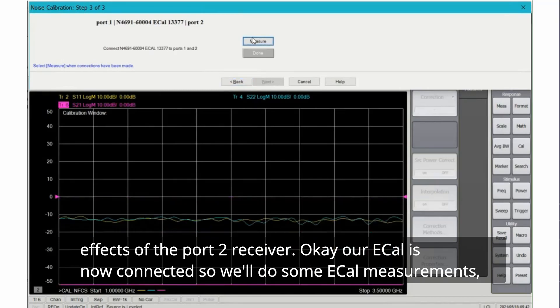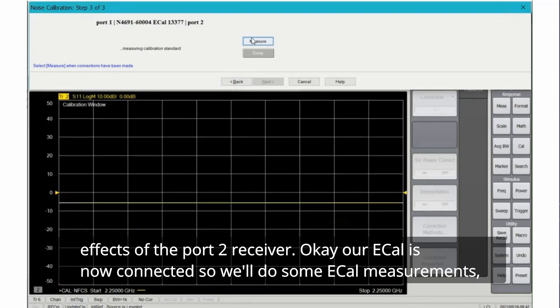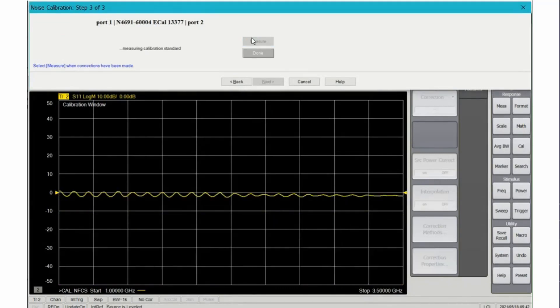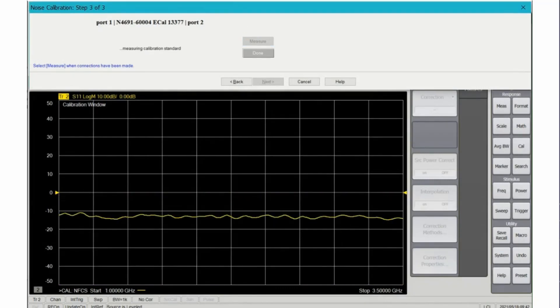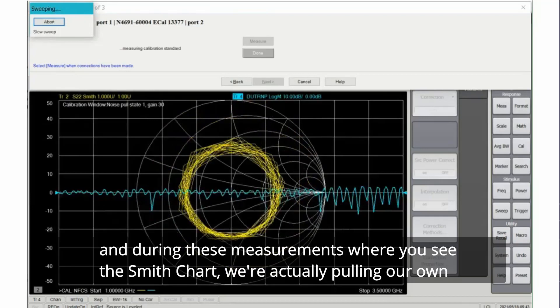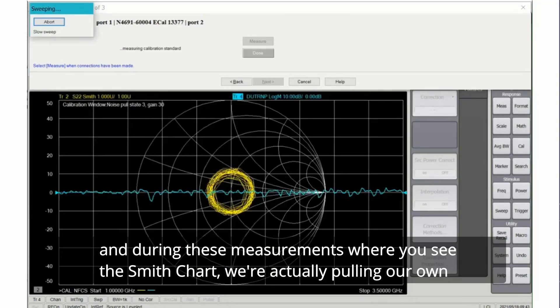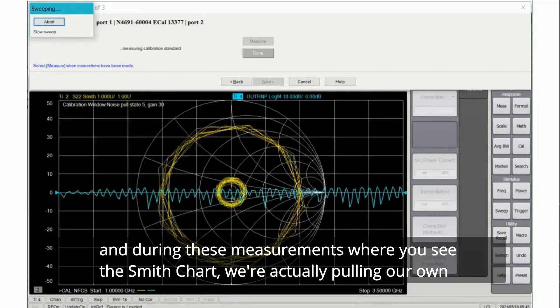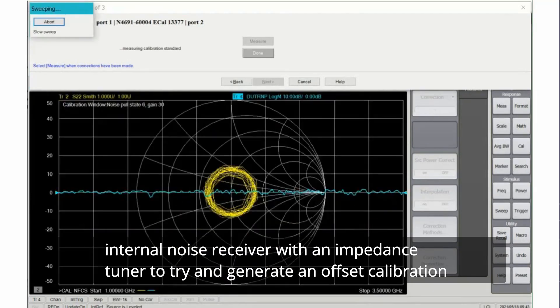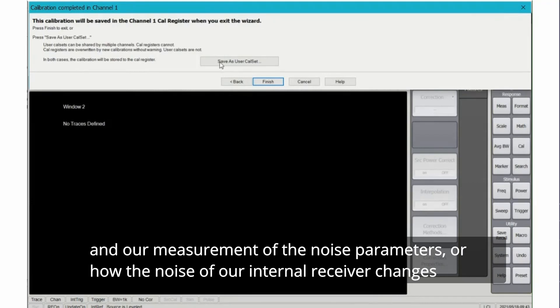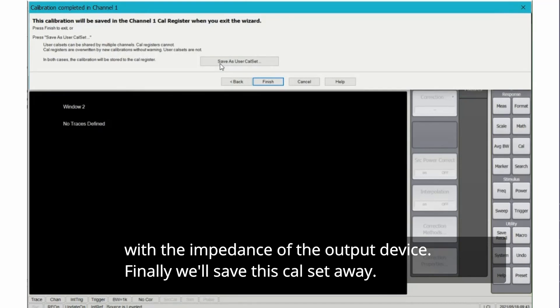Our ECAL is now connected so we'll do some ECAL measurements. During these measurements where you see the Smith chart, we're actually pulling our own internal noise receiver with an impedance tuner to try and generate an offset calibration or a measurement of the noise parameters, or how the noise of our internal receiver changes with the impedance of the output device.